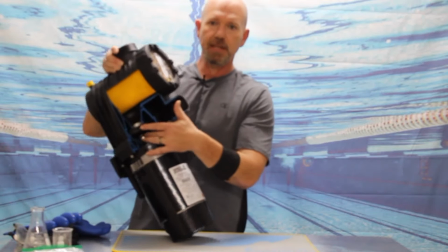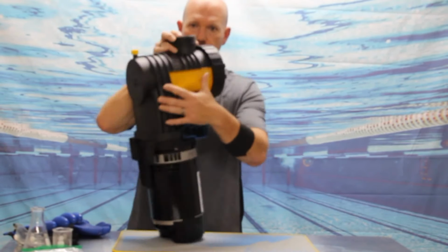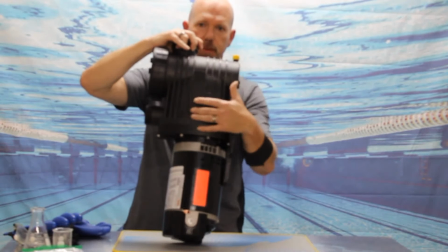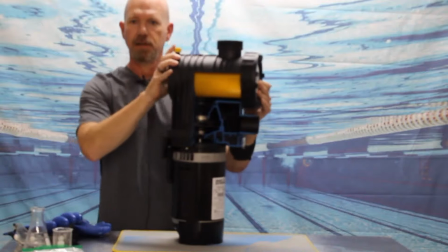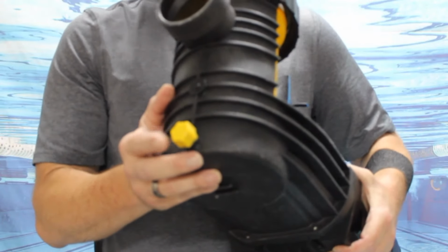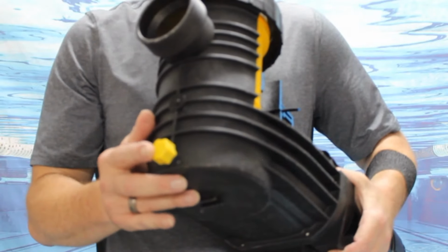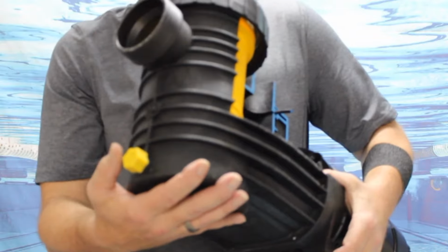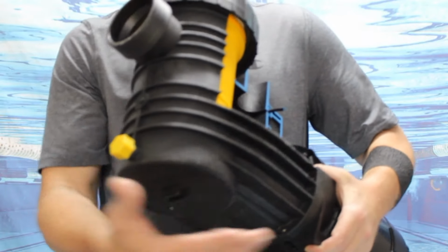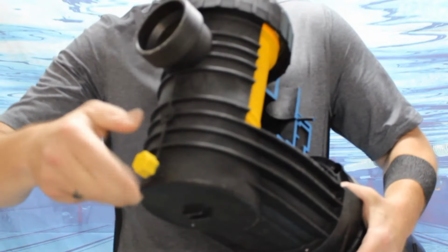If that looks to be in good shape, the next thing I want to check is my pump housing. I want to give everything a once over, make sure I don't see any visible cracks in my pump housing itself. If we're good there, I want to check my freeze plug. You'll have either one or two depending on the style of pump that you have. You'll always have one in the front. You may also have one on the side. Again, it depends on the style of pump. Beneath that, we'll either have Teflon tape or a gasket. Take it off, take a look beneath it, see what you have.